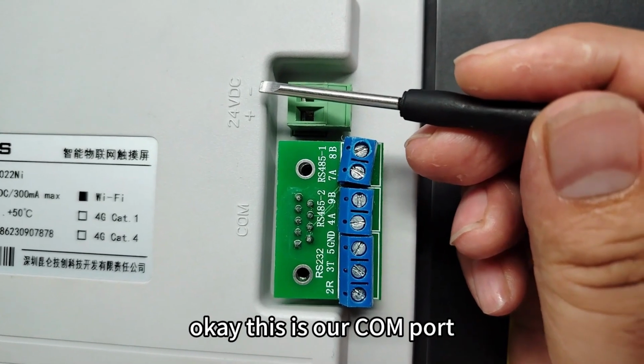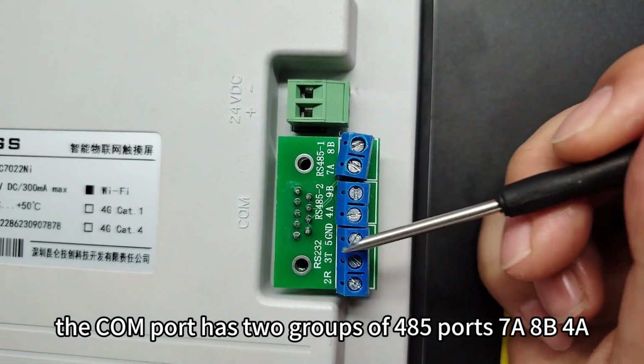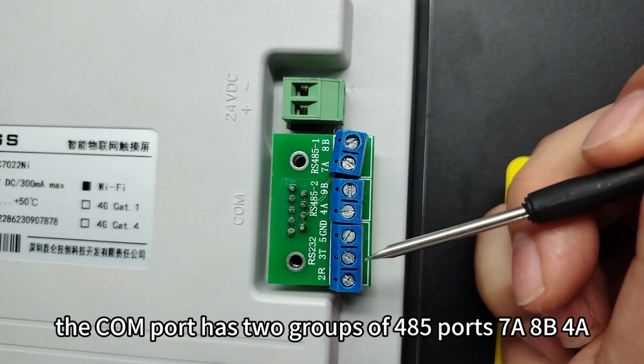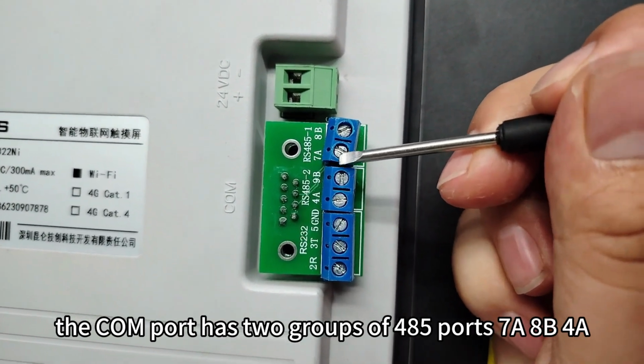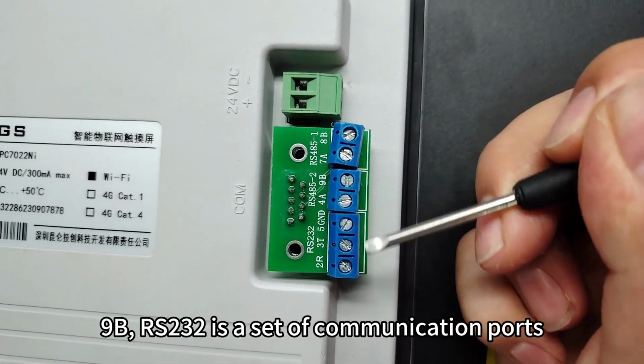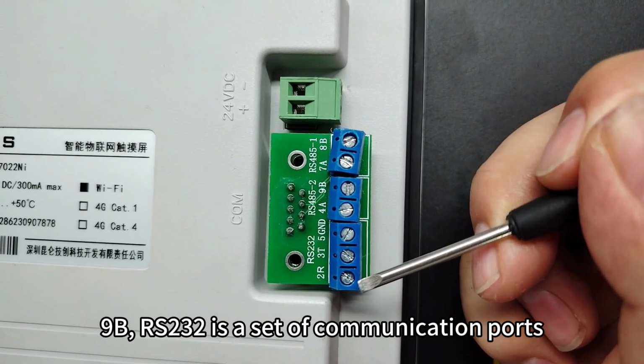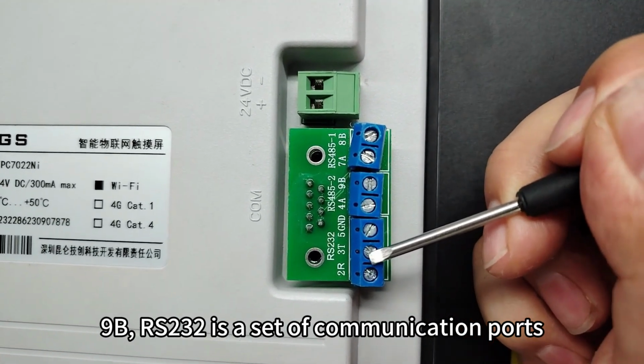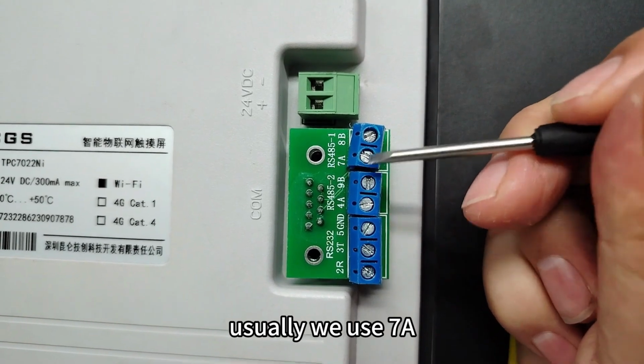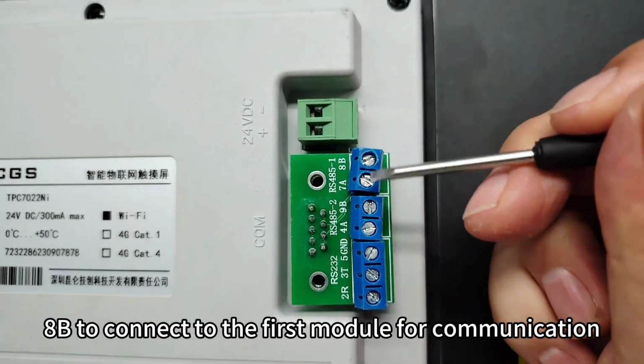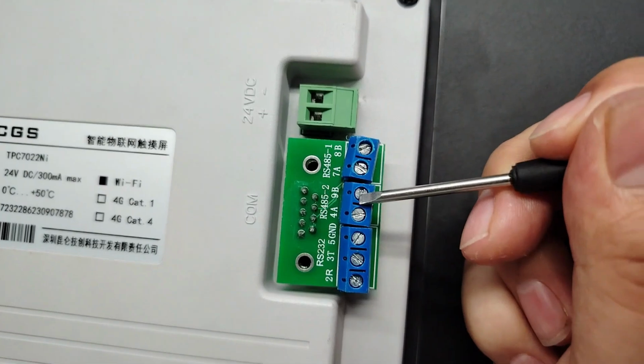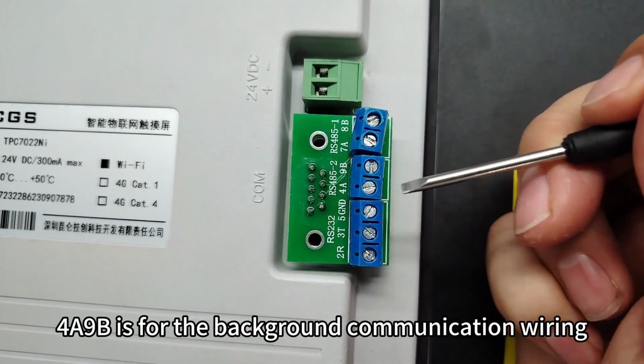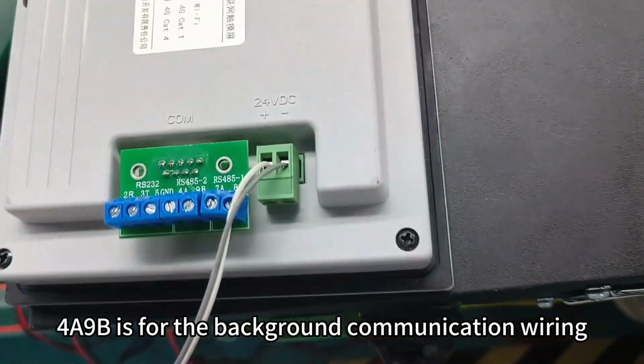Okay, this is our COM port. The COM port has 2 groups of 485 ports, 7A, 8B, 4A, 9B. RS232 is a set of communication ports. Usually, we use 7A, 8B to connect to the first module for communication. 4A, 9B is for the background communication wiring.